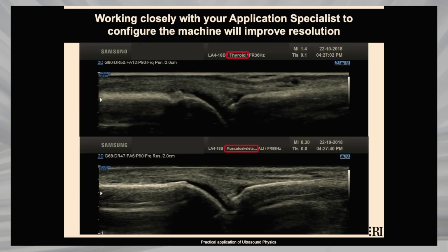The next thing is that if you look at the presets, look at the difference. So this is one that's been done on a thyroid preset, the one at the top. Again, if we have the lights down, it would really help. You'll see the difference that on a thyroid preset, everything is very processed and it will be blended. Whereas on a musculoskeletal, we have a much sharper algorithm and therefore the images will be much sharper. You'll get much better cortical detail than you would if you use the wrong preset.